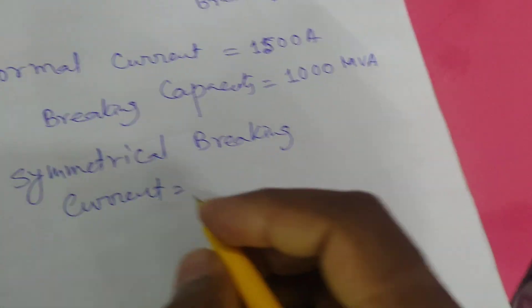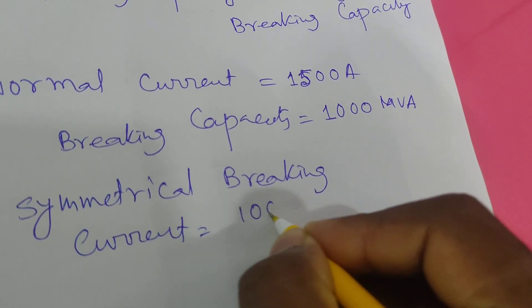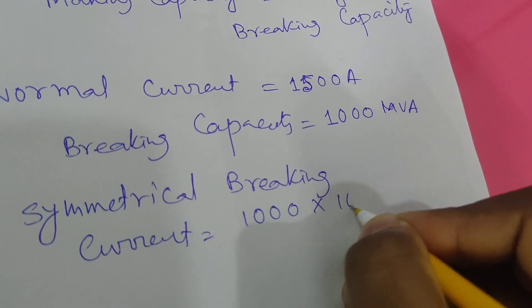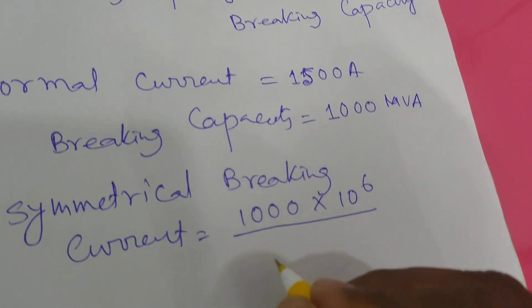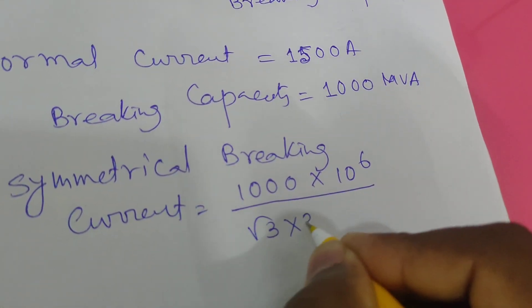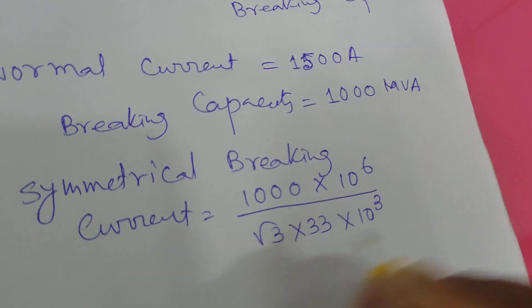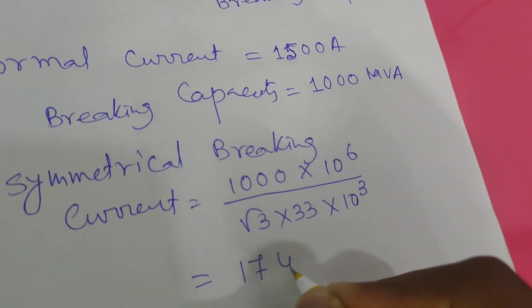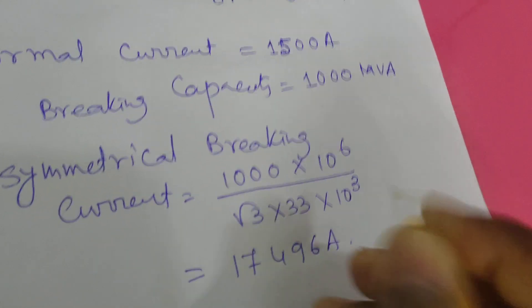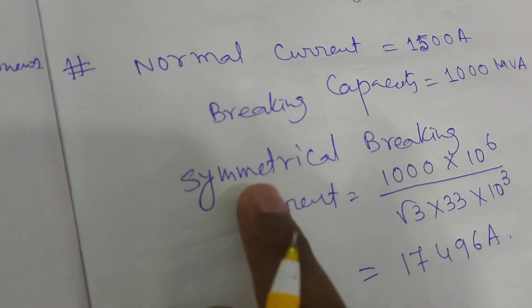The symmetrical breaking current equals 1000 × 10⁶ divided by (√3 × 33 × 10³), which gives 17,496 ampere. So this is the symmetrical breaking current.